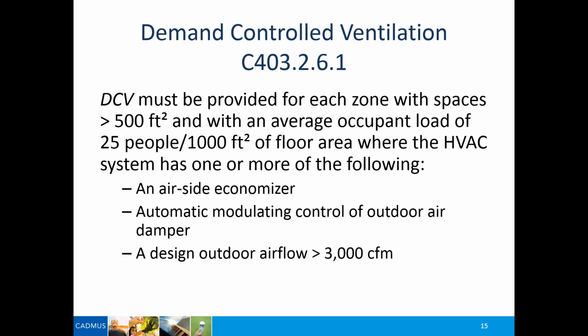So instead of dumping this outdoor air to the great outdoors, it has to go through a heat exchanger system to capture the cool of that air, so that when we bring air into the space, we can pre-cool that air before it hits the cooling system. So this is demand control ventilation. This has been in the code for a few cycles. I can't remember if it's in the 2006 or not. It's an ASHRAE 2. The threshold is a space greater than 500 square feet with an average occupant load of about 25 people per 1,000 square feet of floor area. You are required to have this type of system.